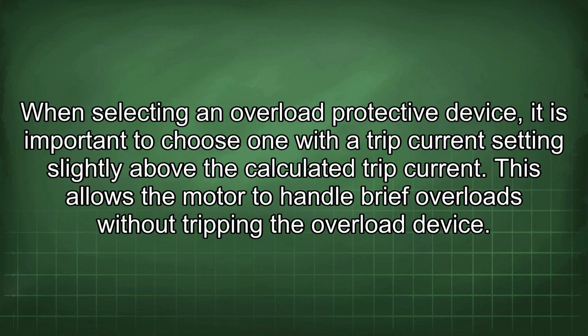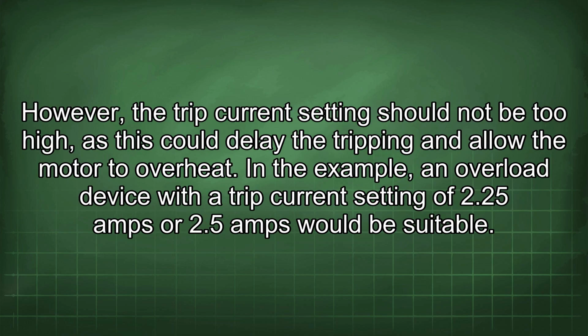When selecting an overload protective device, it is important to choose one with a trip current setting slightly above the calculated trip current. This allows the motor to handle brief overloads without tripping the overload device. However, the trip current setting should not be too high, as this could delay the tripping and allow the motor to overheat. In the example, an overload device with a trip current setting of 2.25 amps or 2.5 amps would be suitable.